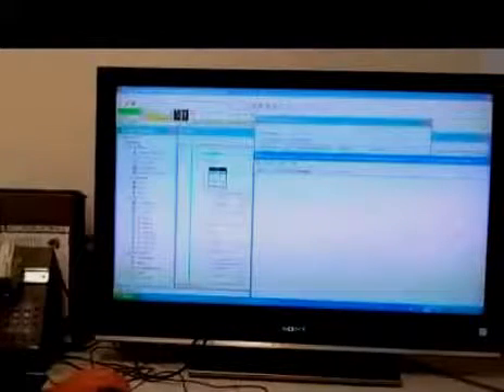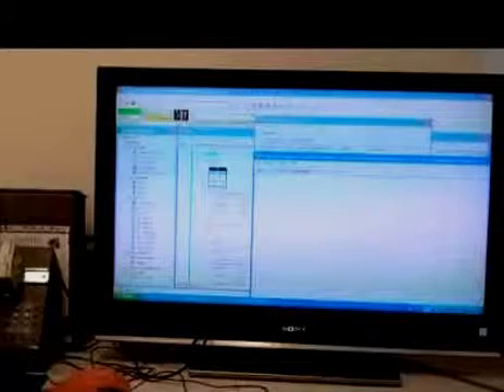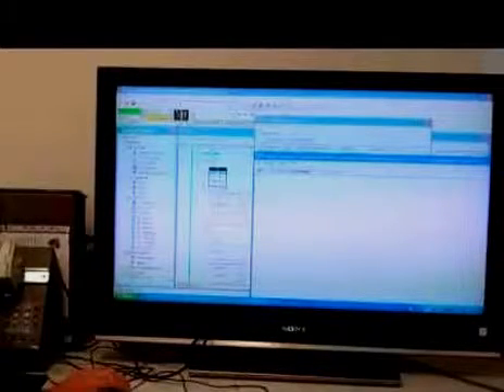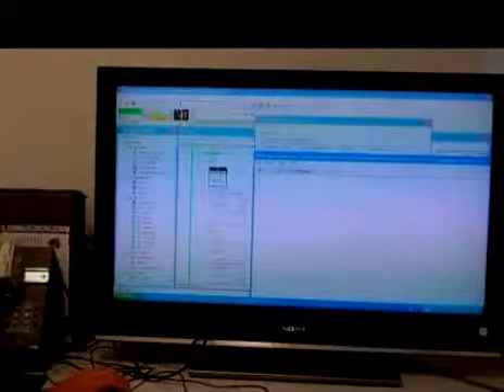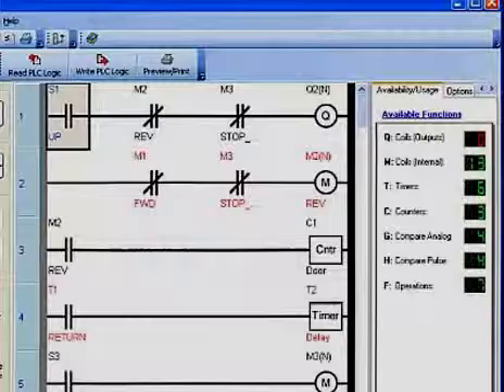The program is entered and viewed via a personal computer connected to the PLC's programming port. The programming unit is used to build, test, and edit the logical sequence that the PLC will execute. Equally important to understand is that the personal computer used to display and edit the PLC's program is not necessary for the PLC's continued operation. Once a program has been loaded to the PLC from the personal computer, the personal computer may be unplugged from the PLC, and the PLC will continue to follow the programmed commands.